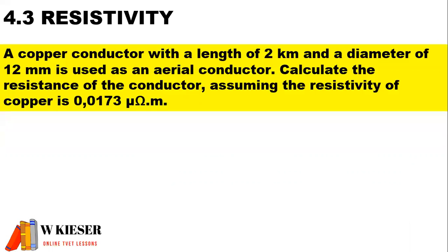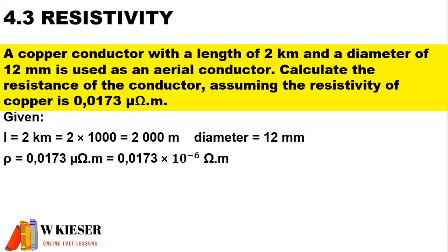In our example for resistivity, a copper conductor with a length of 2 kilometers and a diameter of 12 millimeters is used as an aerial conductor. Calculate the resistance of the conductor, assuming that the resistivity of copper is 0.0173 micro-ohm meters. The length is 2 kilometers, so to convert kilometers into meters we multiply by 1,000 — therefore the length is 2,000 meters. The diameter is 12 millimeters, so we still need to work out the cross-sectional area. The resistivity is 0.0173 micro-ohm meters, and to convert micro-ohm meters into ohm meters we multiply by 10 to the power of minus 6.